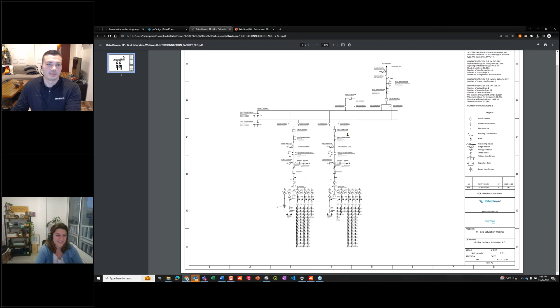In my selection of the substation layout, we can see the double bus bar configuration I had selected earlier. Going directly to our capacitor banks, we're going to see 2 of them implemented here at the MV switchgear level, at the entrance of our substation.